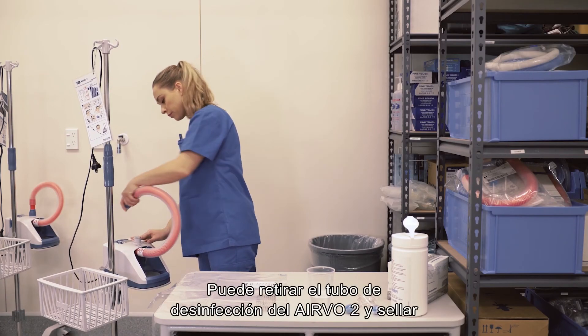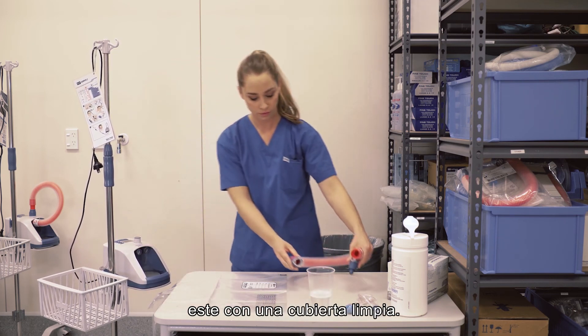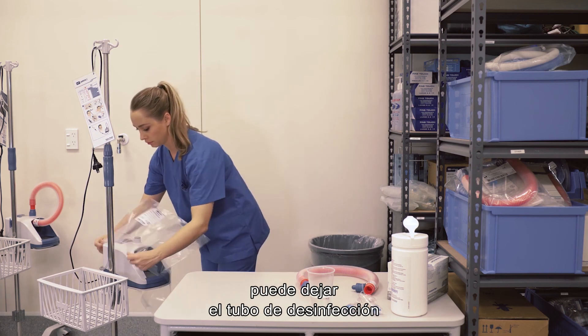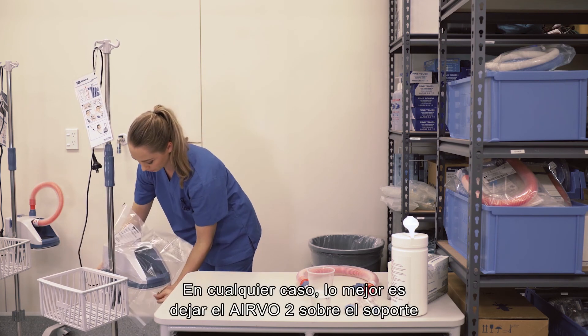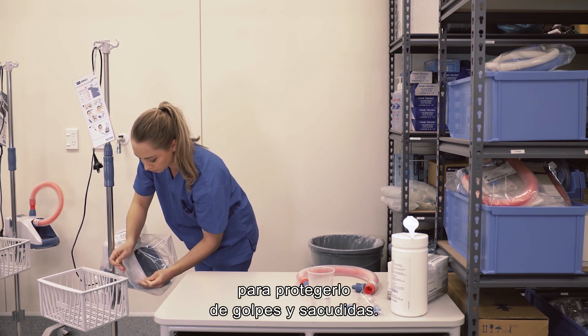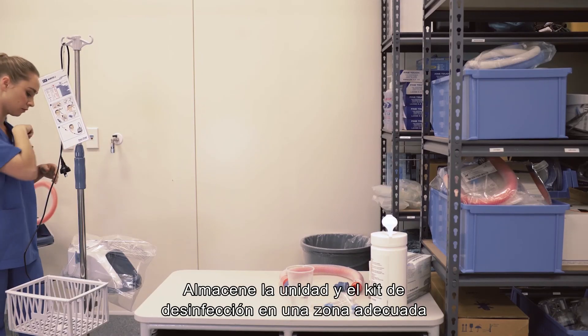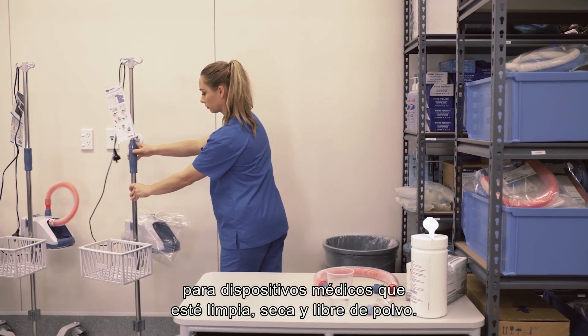You can remove the disinfection tube at this stage and seal the AIRVO 2 with a clean storage cover. If you are not using the clean storage cover, you may prefer to leave the disinfection tube in place for storage. In either case, it is best to leave the AIRVO 2 on the stand to protect it from bumps and knocks. Write your name, the disinfection date and the disinfection number on the space provided on the clean storage cover. Store the unit and disinfection kit in an area suitable for medical devices which is clean, dry and dust free.